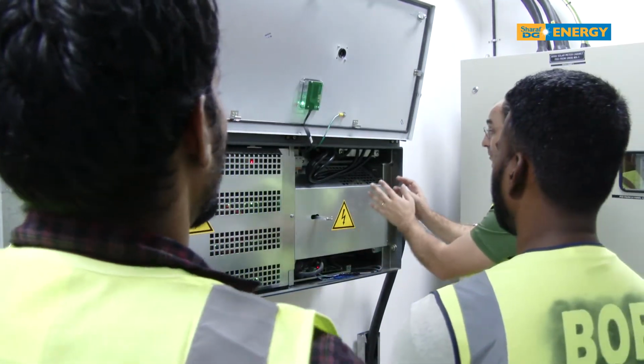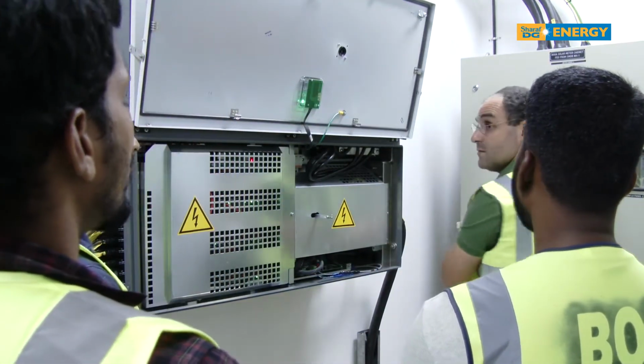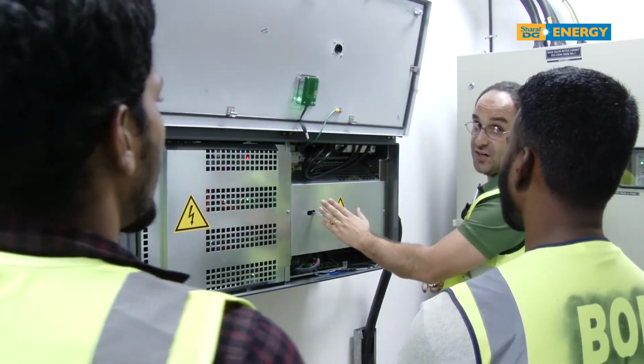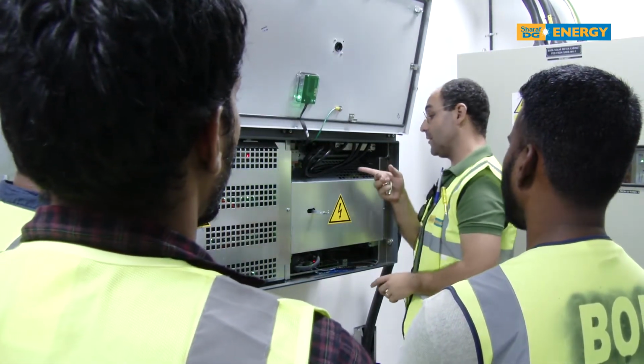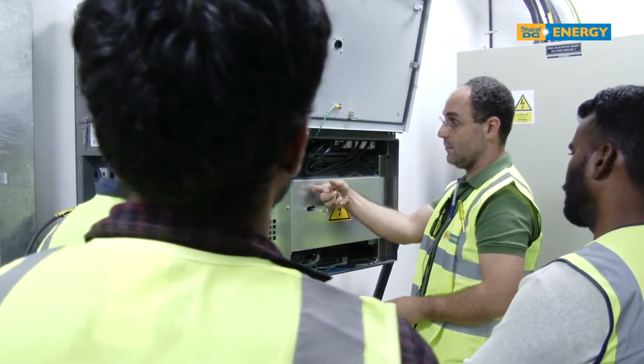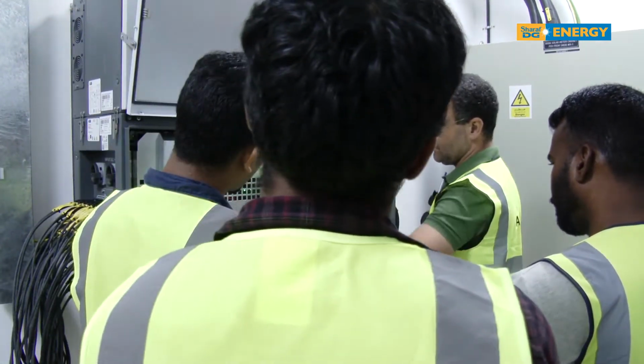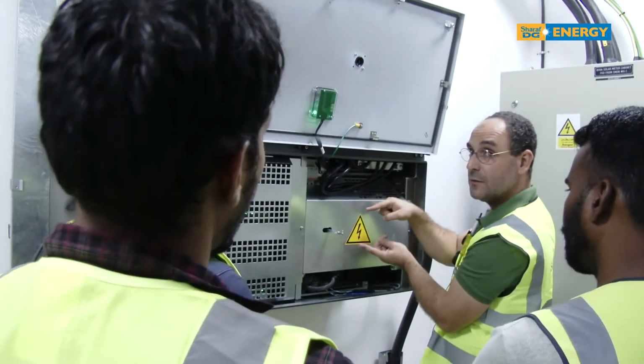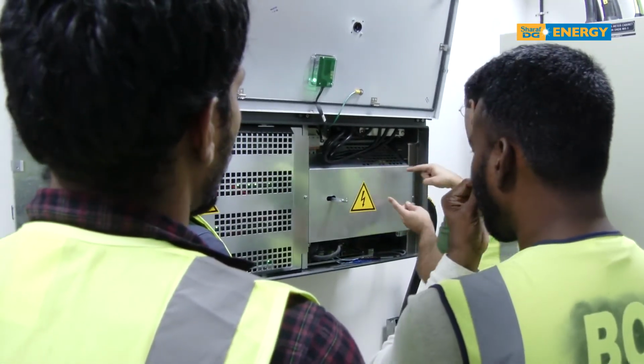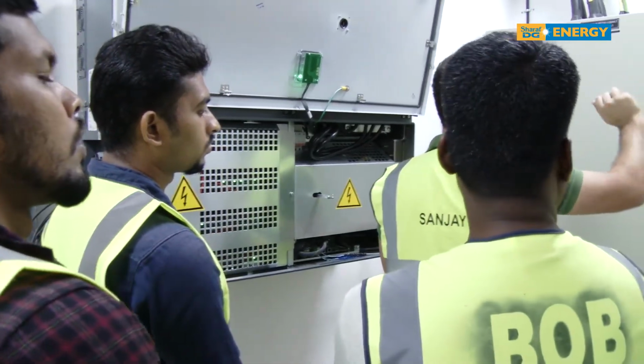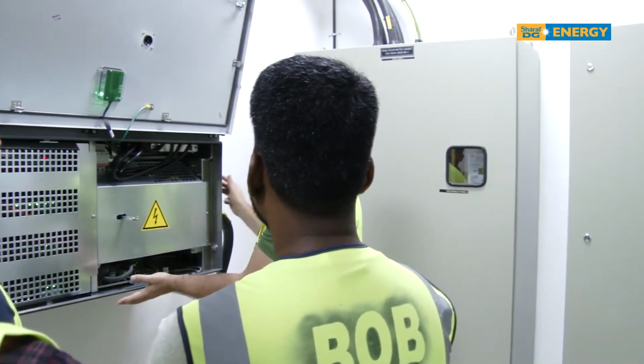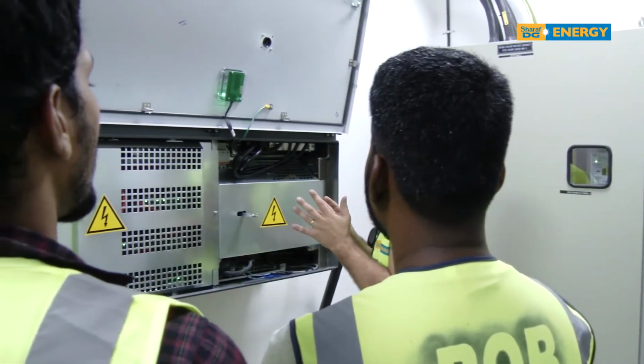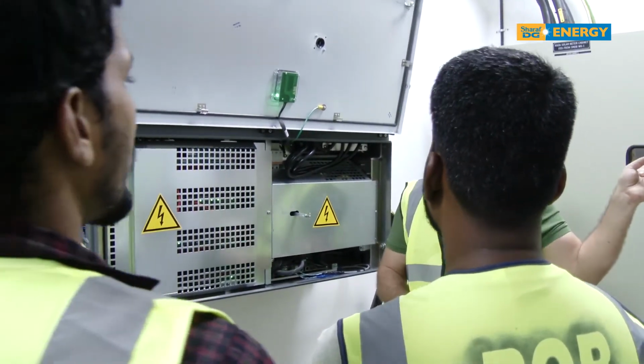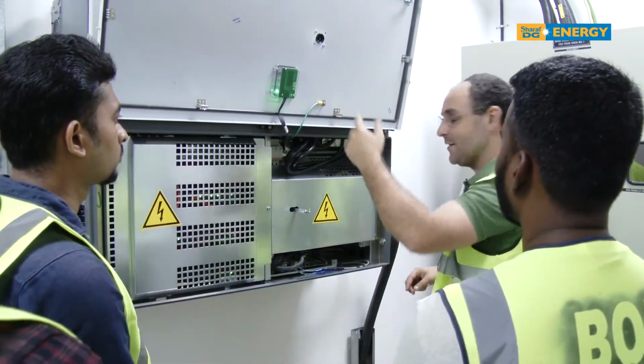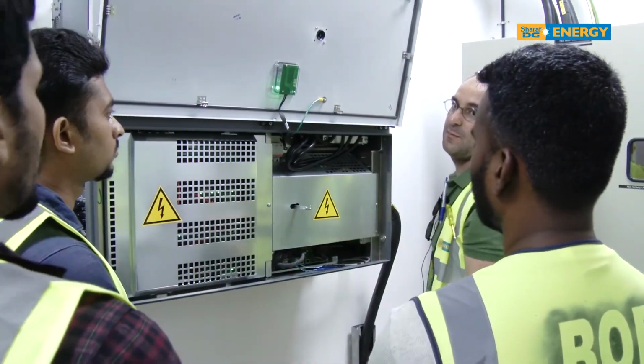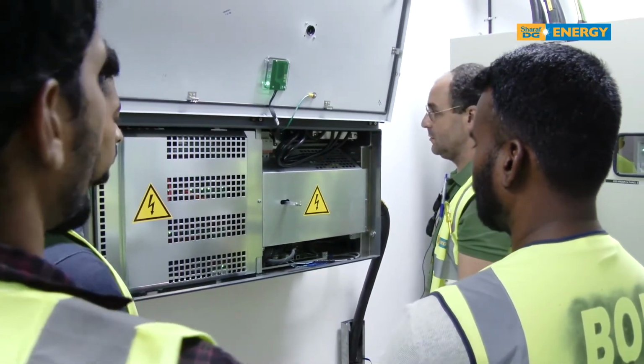If you want to work from this side to that side, isolating here is not enough, because your cables are here. So if you isolate here, you still have potential on these cables. You need to go back to that panel, isolate the panel and the small breaker, and you're good. If you want to do work from the main breaker to the DC side, you have to switch off the rest of the system.